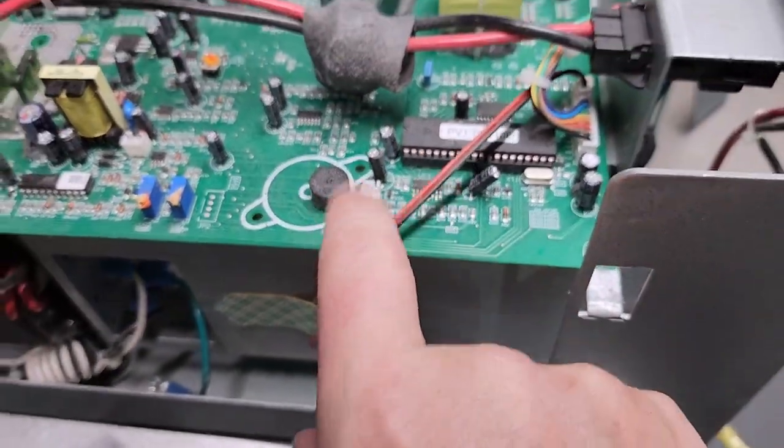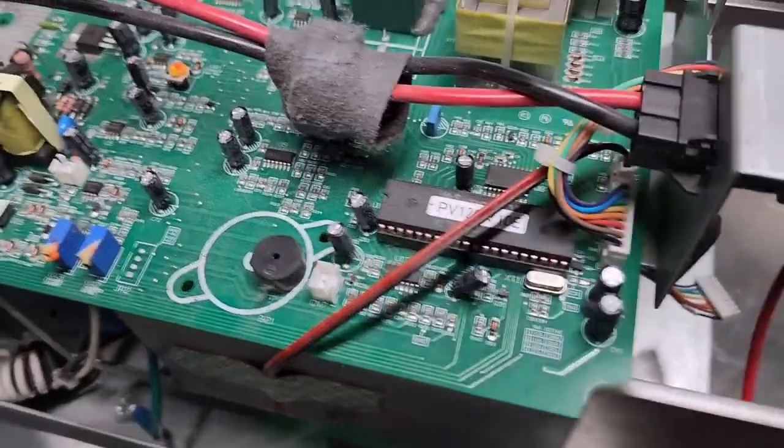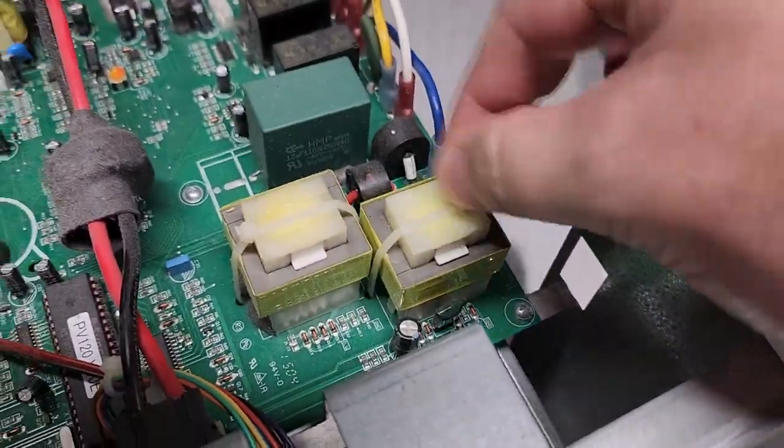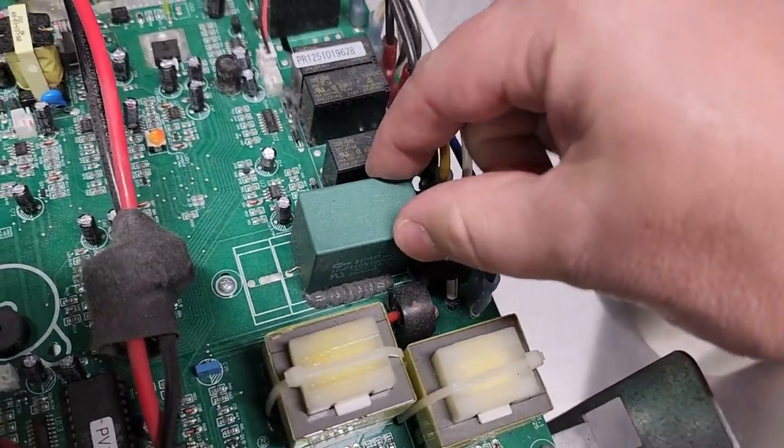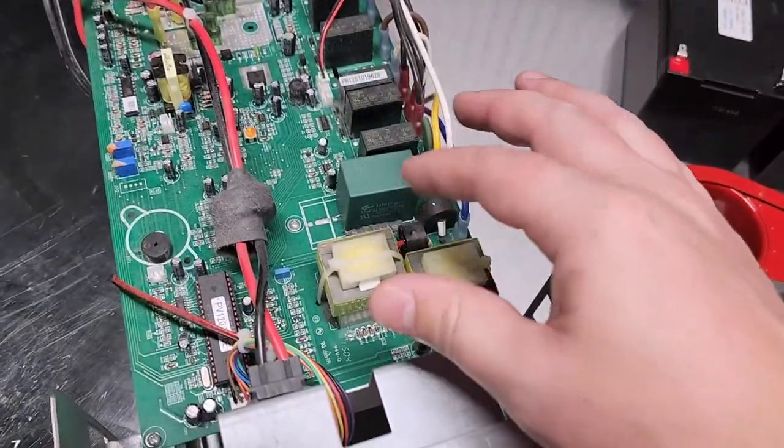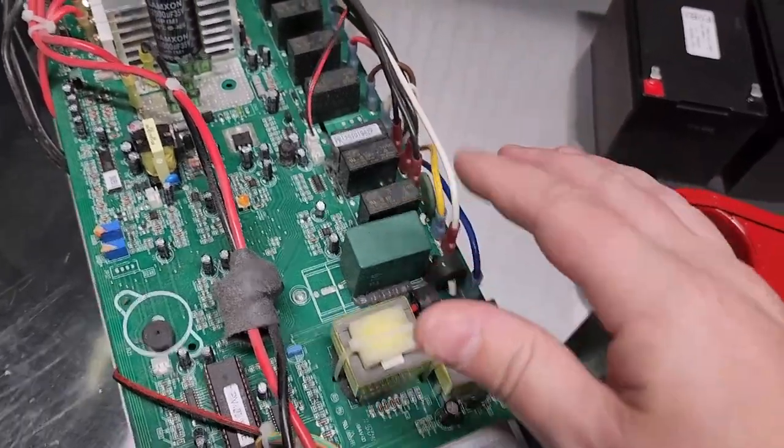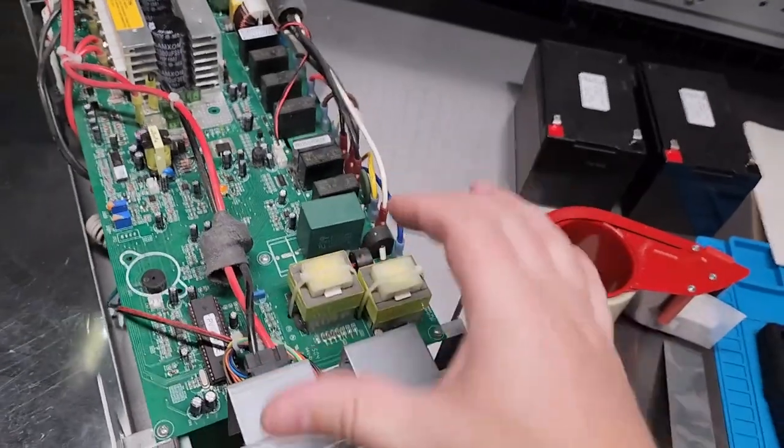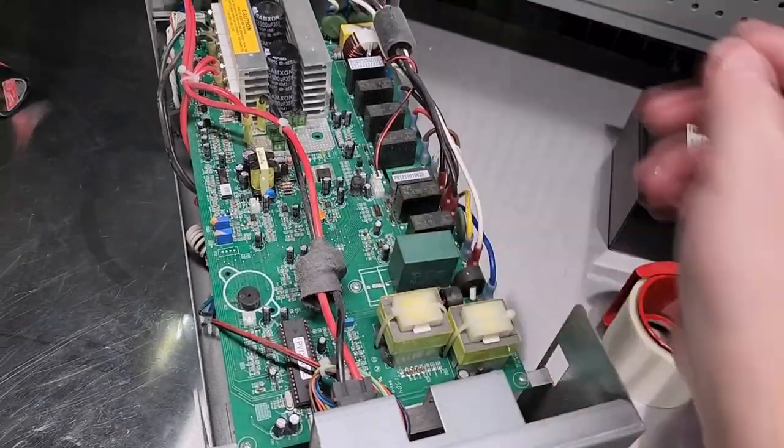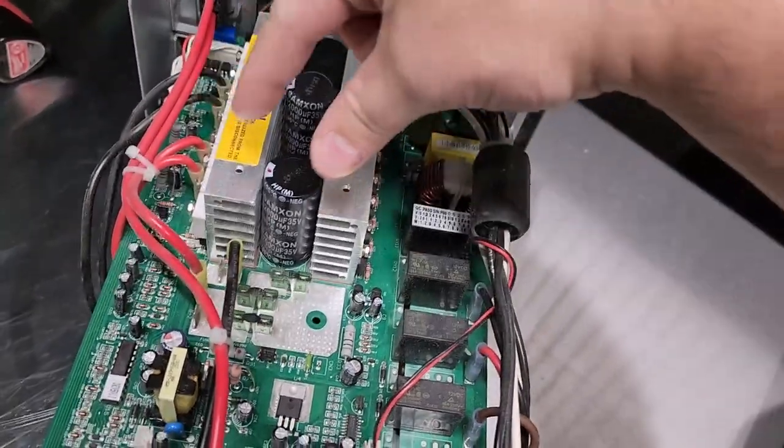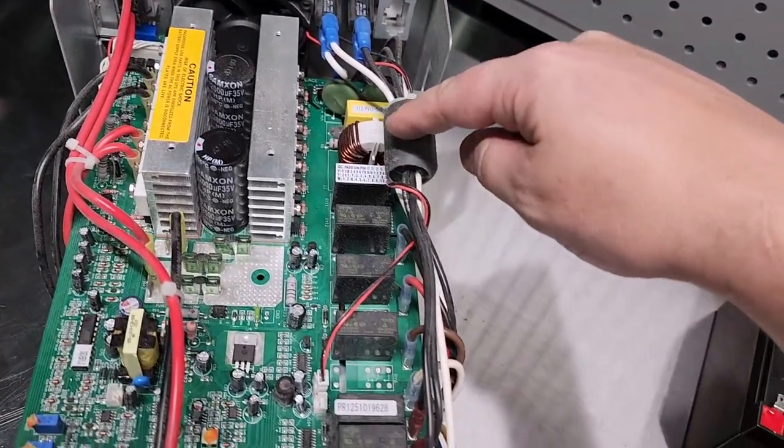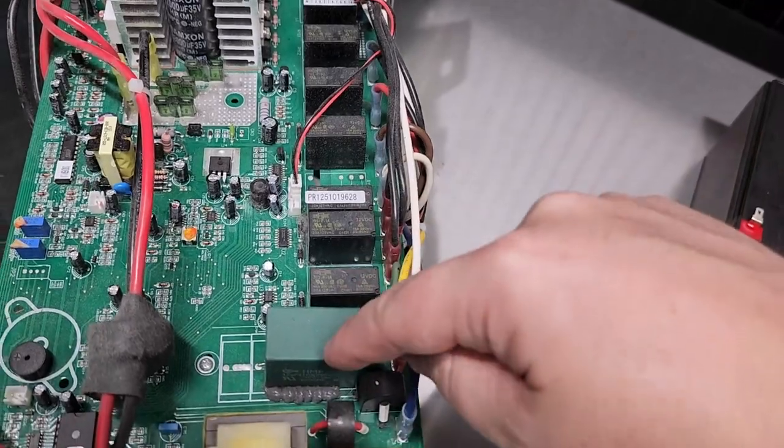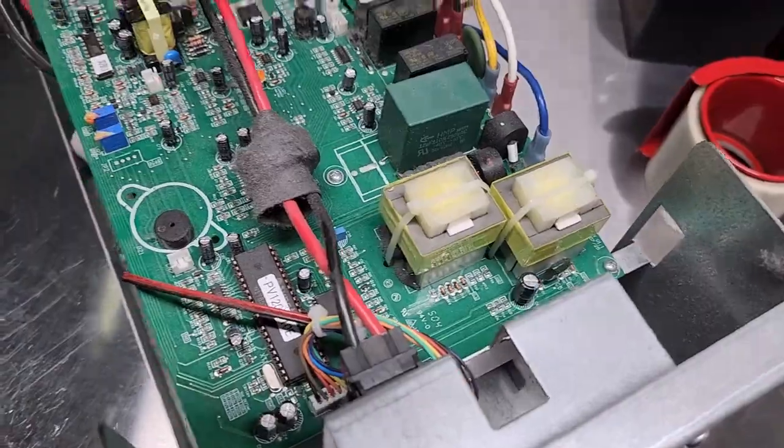It says right here, risk of electric shock, hazardous live parts. I've shocked myself on heat sinks before. You would think that they're not at high voltage potential, but they most certainly are often on these guys. I check all the electrolytic capacitors, make sure that everything's good, make sure that there's no lint balls on here. Make sure that the alarm speaker doesn't have any lint inside it. Also, you see how these guys are all secured down, and they also have the goo. That's to make sure that through its rough life, vibration, that all these components stay down because they have a lot of mass.